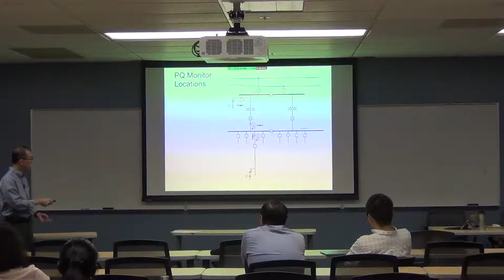You can also put your power quality monitor right at the terminal of the device you're trying to evaluate. In this case, perhaps you want to assess the health condition of a capacitor, so you put it right there - all the currents you see are capacitive current, there's no other current, not supposed to be. So whether there is an energizing or de-energizing, it must have to do with capacitors.